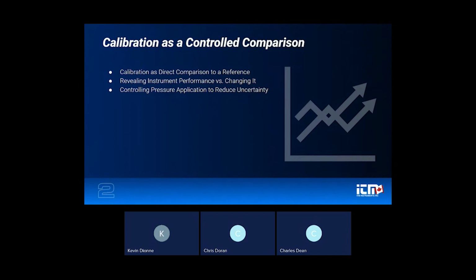A common misconception that we'll see with customers is that calibration somehow improves the instrument's accuracy. I need to get a calibration on this pressure gauge so that it's more accurate. In reality, calibration does not change the performance of the instrument. It simply reveals it. It tells you how the instrument is behaving relative to its specifications at the time of your test.